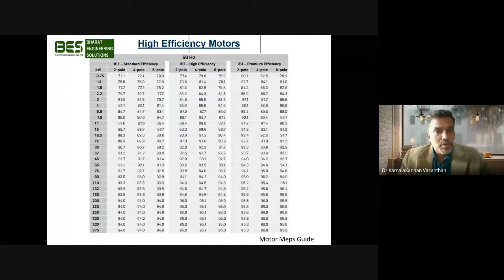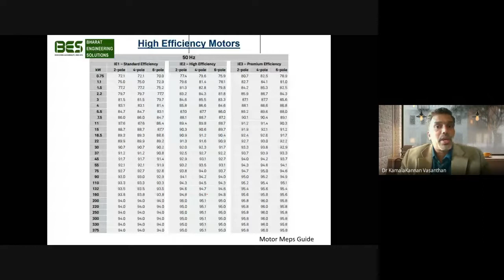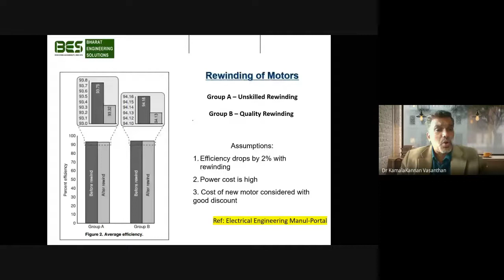And do ensure that high efficiency motors are used. Multiple efficient premium motors have come up, IE2, IE3, and even IE4. Do ensure the pumps are fitted with appropriate premium efficient motors. And coming to rewinding of motors, what we found is that rewinding with unskilled and skilled laborers makes a difference of almost 0.5% in the efficiency of motors. And what we saw in the electrical engineering manual is that efficiency drops almost 2% with every rewinding. So ensure that the rewinding cost is considered against a new motor purchase. I think with some good discounts from initiatives like EESL, we will be able to do good motor replacements too. And these were the basic pump audit processes we follow.